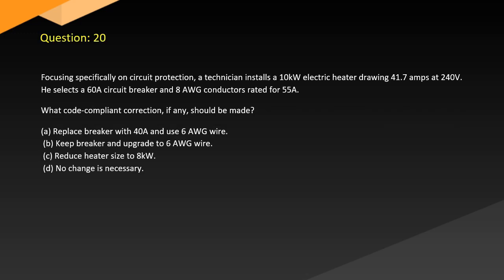Question 20. Focusing specifically on circuit protection, a technician installs a 10 kW electric heater drawing 41.7 amps at 240 V. He selects a 60-amp circuit breaker and 8 AWG conductors rated for 55 amps. What code-compliant correction, if any, should be made? A. Replace the breaker with a 40-amp and use 6 AWG wire. B. Keep the breaker and upgrade to 6 AWG wire. C. Reduce heater size to 8 kW. D. No change is necessary.